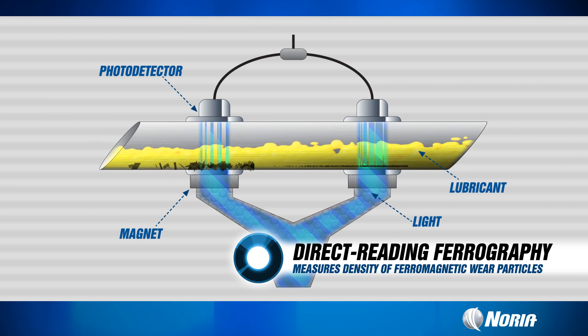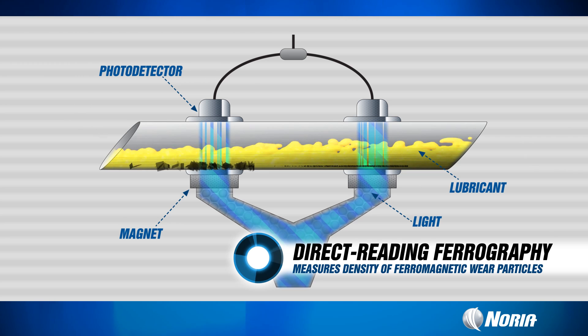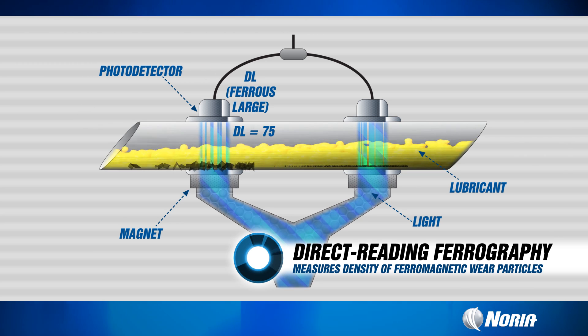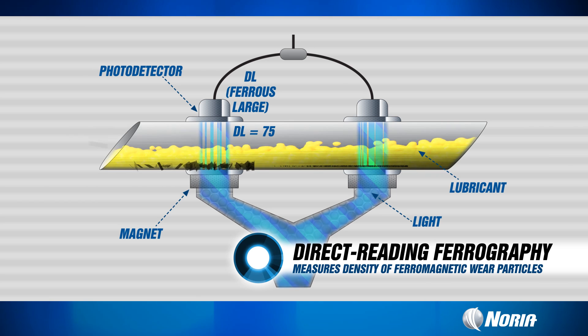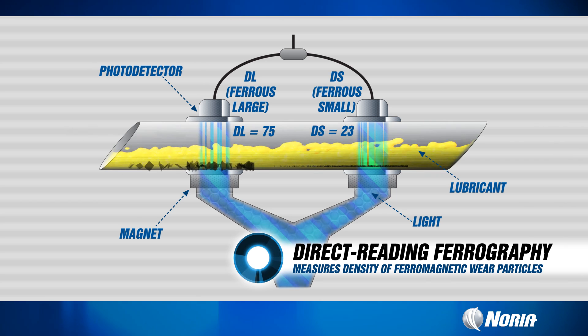Light is then transmitted through the sample, with photo detectors on the instrument measuring the amount of light passing through that sample. The results we get from direct reading ferrography are ferrous large, which are those particles greater than 5 microns in size, and ferrous small, which are those particles less than 5 microns in size.